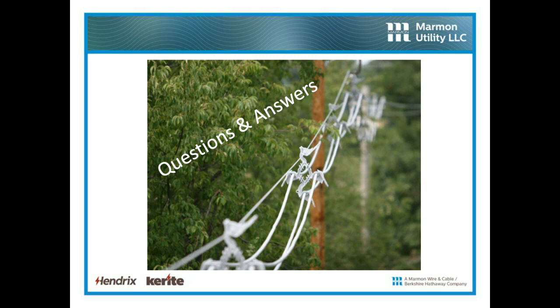Related to that, what is the maximum surface current in each phase? Excellent. The maximum surface current in each phase is going to be the same. There is a graph that gives you the maximum surface current for each conductor size for each kV rating. Say if I'm at 15 kV and I have a number 2 conductor, that surface current might be 0.2 milliamps. But if I have a 795 or 1192 kcmil conductor, that surface current could be two or three times that, well, twice it anyway. So if I have a greater surface area, there's more ability for wet leaves wrapping around that conductor to contact current. So it's actually milliamps per foot.